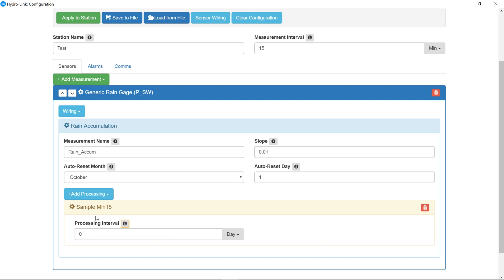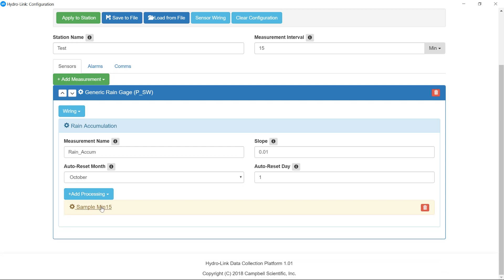Also on rain, the sample is the only processing you can do. On other measurements, you can do an average or a max and min. In most of the cases, you're just going to do a sample, an instantaneous value at that 15 minute mark. If I decided I didn't want to do this, I can always come over here and delete it, or I can delete the whole gauge.